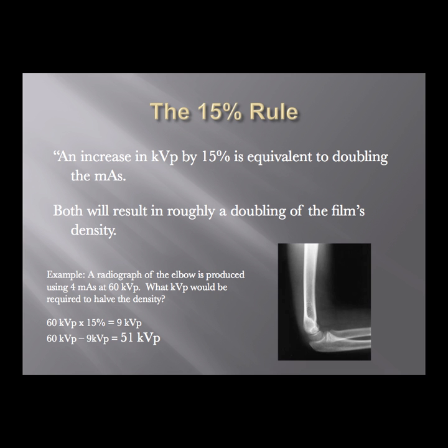When we talk about the 15% rule, it only takes an increase in KVP of 15% to essentially double the density. The 15% rule states that an increase in KVP by 15% is equivalent to doubling the mAs. So if you want to double your density, you have two choices: double your mAs, or increase your KVP by 15%. However, you have to be careful when making changes in KVP because it's also the controlling factor for contrast — you may succeed in changing density but pay a price in contrast.